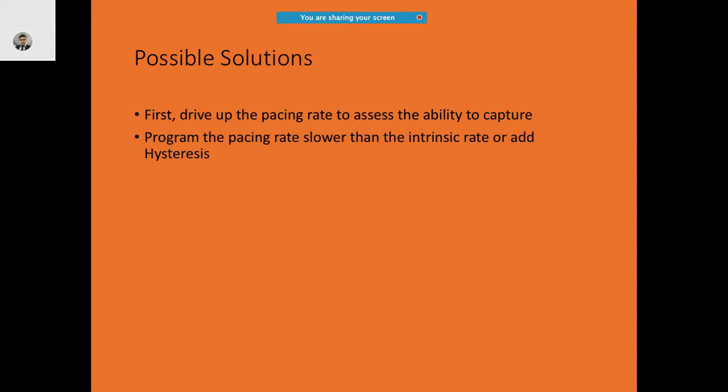Possible solutions for fusion and pseudo-fusion include: drive up the pacing rate to assess the ability to capture, program the pacing rate slower than the intrinsic rate, or add a possible hysteresis.